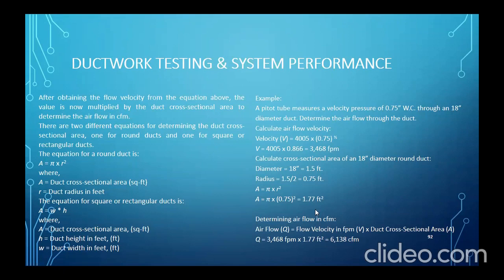So velocity, radius, so pi times 0.7 equals 1.77 square feet. So determining the airflow in CFM, airflow Q is equal to airflow velocity in feet per minute times the cross-sectional area. Q is equal to 3468 feet per minute times 1.77, or 6138 CFM.